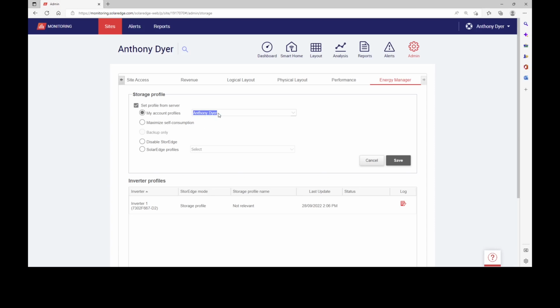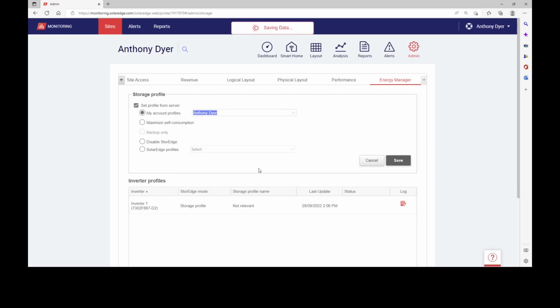And since the test profile is active on the storage profile, we can now hit Save. It takes some time for that storage profile to become active, but once it does, you'll see that there is 5 kilowatts being charged into the battery. What we're now going to do is go outside and add the charge of the car charger on top of the battery charger, and we're going to look at maximum demand.